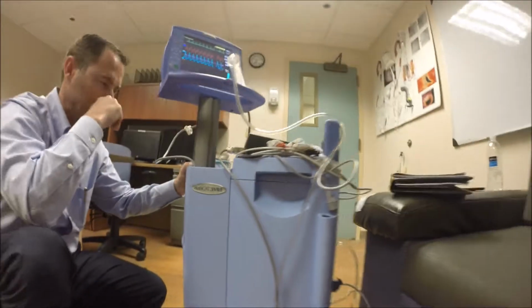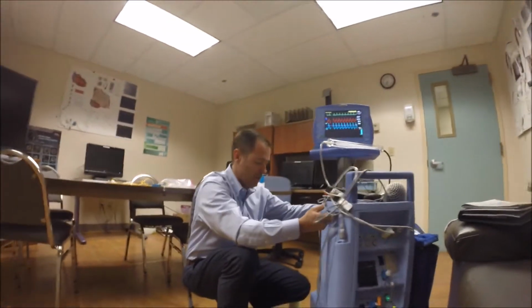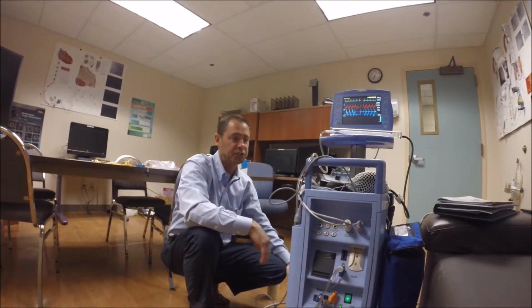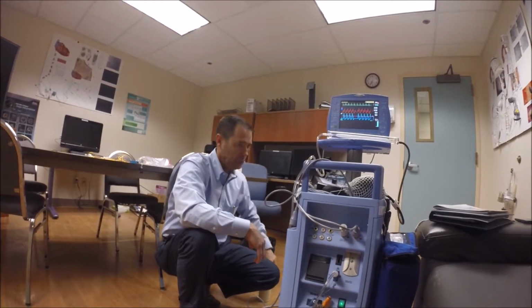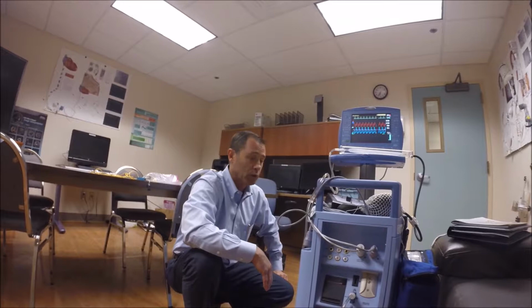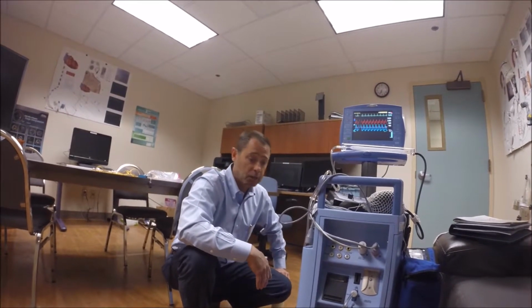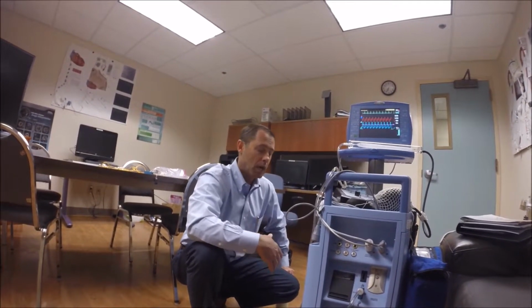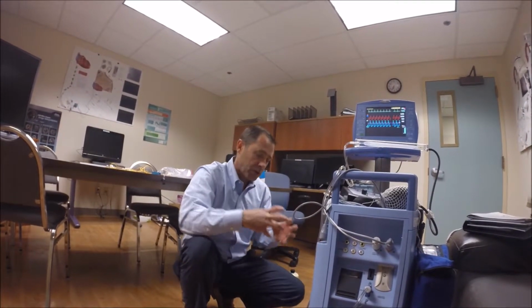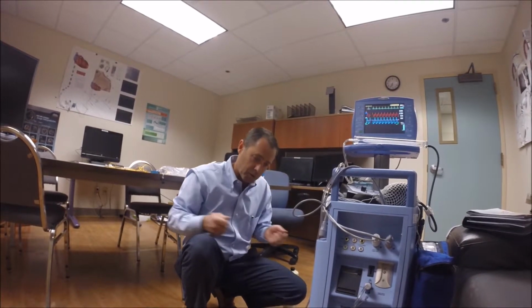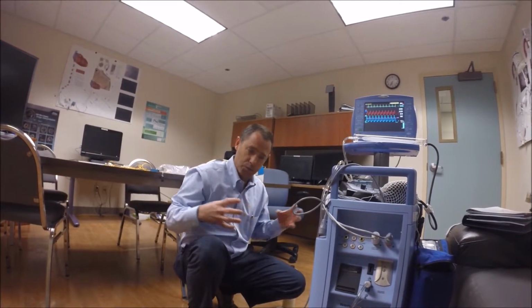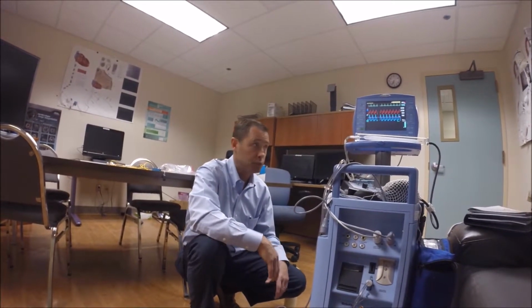Then just plug that right back in and close it down. Lock it, shut it. No adjustments are needed for in flight - the pump automatically adjusts to altitude, so there's no need to make any adjustments. You're not going to get pressure alarms or anything like that, so it's very transport friendly. In fact, you can lay this pump down or turn it upside down. It has what's called a stepper bellows mechanism, just like the bellows on a fireplace. It is not gravity driven, so you can just lay it down if you need to.